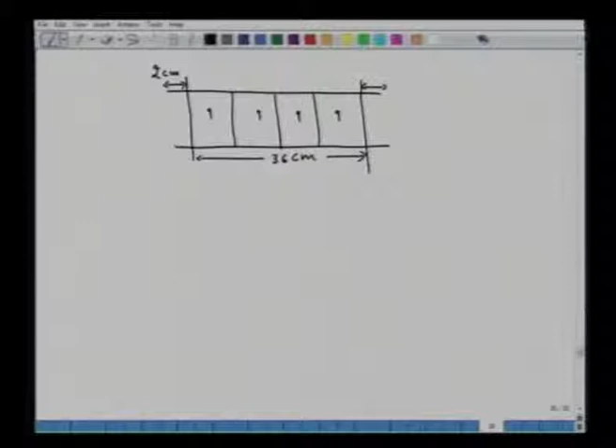Now, one of the important messages that I want to give you when you want to design a furnace, see that the ends of the furnace are thickly wound as compared to the middle of the furnace. Why? Because those ends will be heated at higher temperature. So, heat transfer will occur from the end to the middle part, so that you can get a uniform temperature zone within the center part of the furnace. So, with this objective, what we do is that in the end portions we take 40 windings here, here also we take 40 windings here. So, we get here 32 windings now and 32 windings now, and that can be very easily accommodated in a length of 36 centimeter.